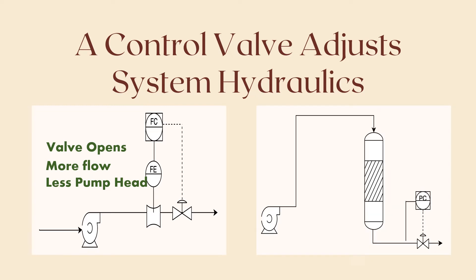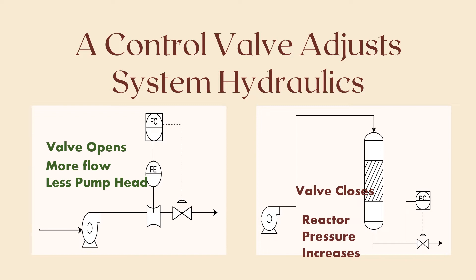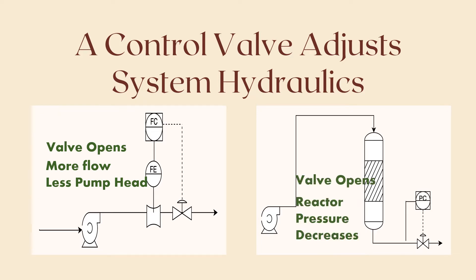In the second example, the control valve doesn't just adjust the flow, but also the reactor pressure. The pressure here is a much more important factor to control, because it will directly affect the reactor conversion, which shall lead to an off-spec product. So here it is not just a matter of controlling the process against some disturbance, but it is more related to adjusting the system hydraulics. Still, the valves are working as a final control element, receiving a signal from the flow or the pressure controller in their control loop.